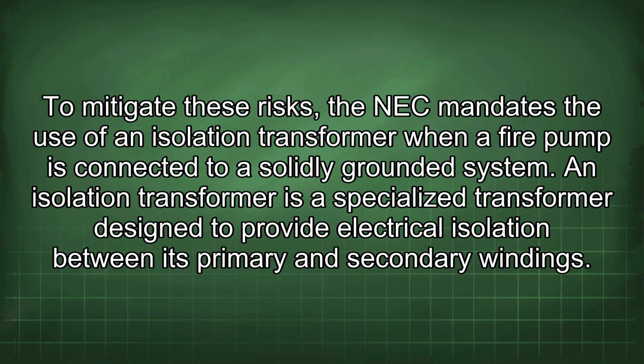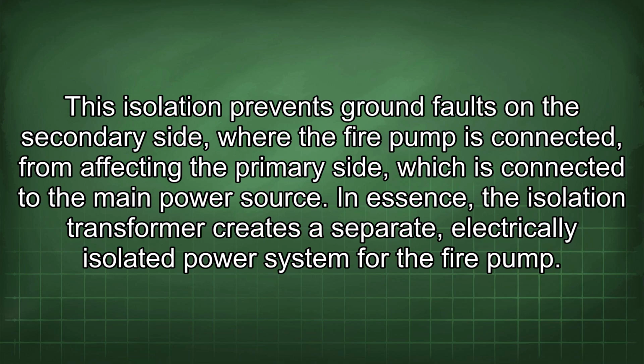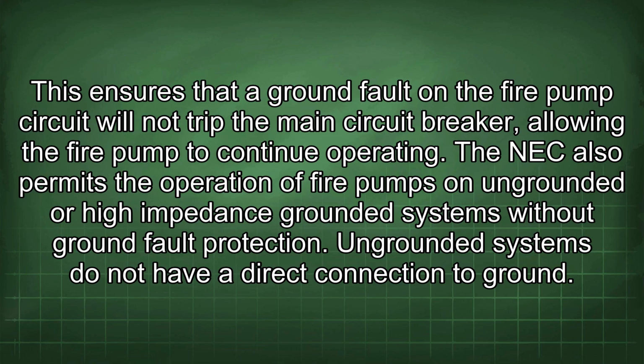a solidly grounded system. An isolation transformer is a specialized transformer designed to provide electrical isolation between its primary and secondary windings. This isolation prevents ground faults on the secondary side, where the fire pump is connected, from affecting the primary side, which is connected to the main power source. In essence, the isolation transformer creates a separate, electrically isolated power system for the fire pump. This ensures that a ground fault on the fire pump circuit will not trip the main circuit breaker, allowing the fire pump to continue operating.